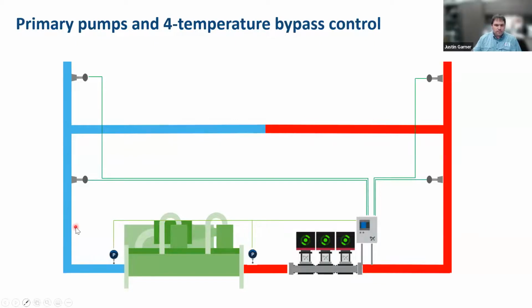This isn't the ideal drawing for that, but basically, if you can imagine that distributed pump out at the air handler in the system, we want to size it from this point in the decoupler out to the load itself. In this case, we're talking about an air handler, and then back again. So whatever the design flow was for that particular air handler, and whatever the friction loss would be from this point and back again, that would be how we size that pump. So I hope that helps answer that.